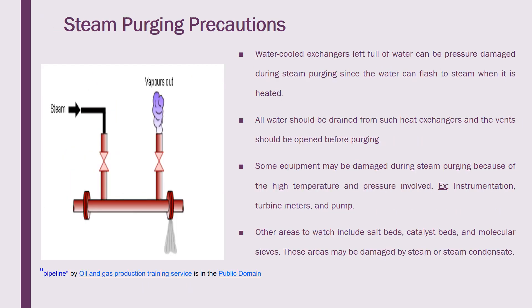Steam purging precaution: while going for steam purging, we must make sure there is no trapped material. If the process material vaporizes because of the steam, it may create an unstable environment inside the equipment. For example, in a water-cooled heat exchanger, if you have not fully drained the water inside the tube and you do steam purging, the water will evaporate with the steam and may create thermal shock - a water hammering effect. This causes stress to the equipment and may cause damage, so we must be very careful.